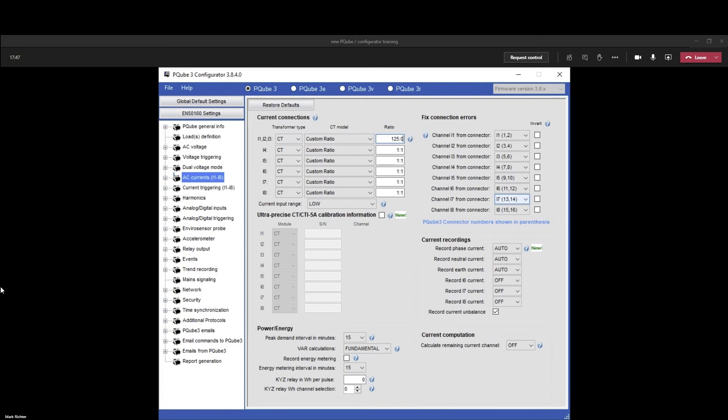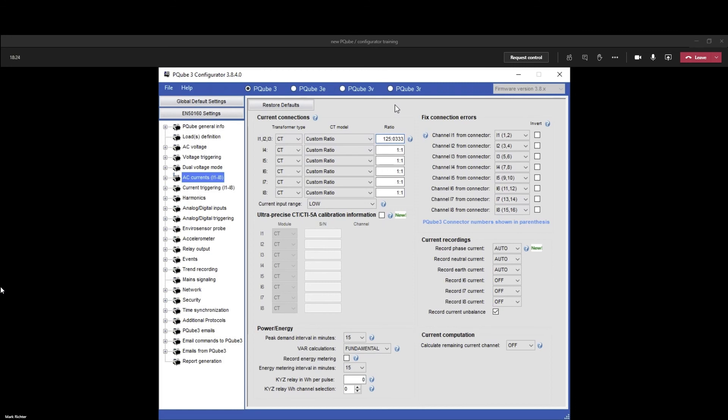What happens if we're installing the meter and someone already has their own existing CTs with a five amp secondary? You'd have one of these which is a five amp CT, and it'll be five amp to 0.333 volts. You get their ratio which may be 2000 to 5. Because you have a five amp CT around their secondary, you make this, you're going to enter the number. So it's now a 2000 to 333.